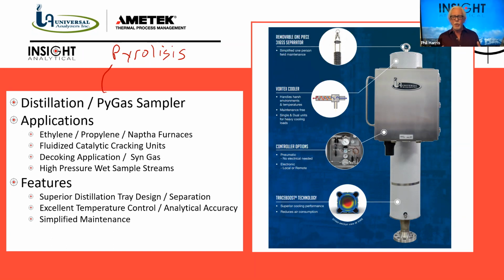These were developed originally for ethylene furnaces and similar applications. When we take ethane and crack it to pull hydrogen off and make ethylene, we can end up making a lot of carbon, along with a lot of steam. These samplers are used to extract a sample from that high temperature, dirty, wet sample stream, cool it, condense the water, take the particles out, return them to the process, and deliver a sample to the analyzer that we can use for analytical measurements and process control.